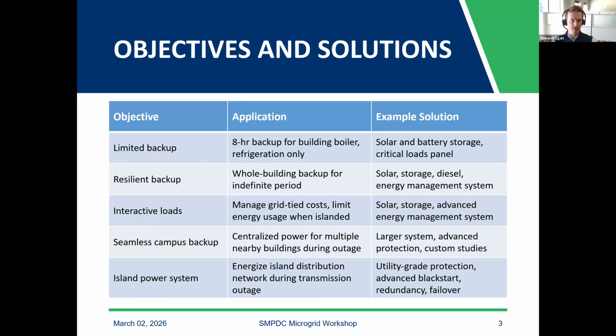That's the core of a limited backup application. For that, you might want a generator that can charge the storage system as well as the PV—still a microgrid. That generator might not run when you're connected to the grid; in fact, for small commercial applications it almost certainly won't. But the system as a whole is still connected to the grid and can operate independently.